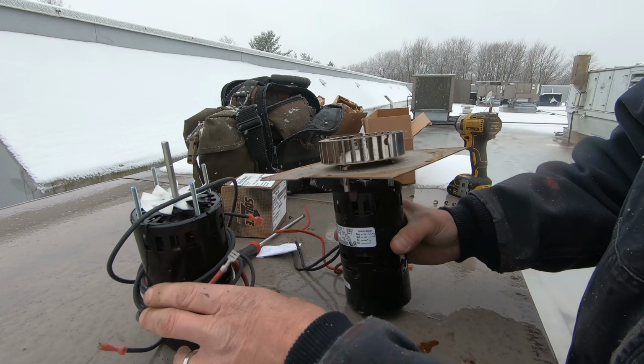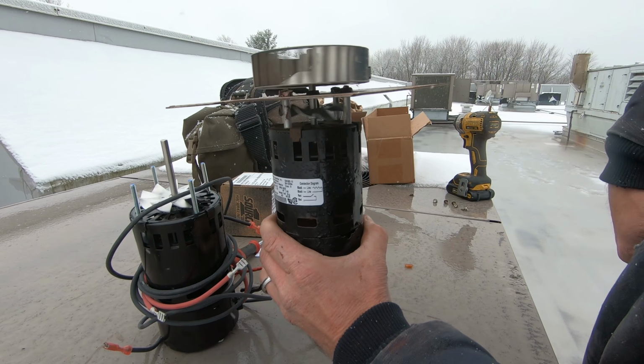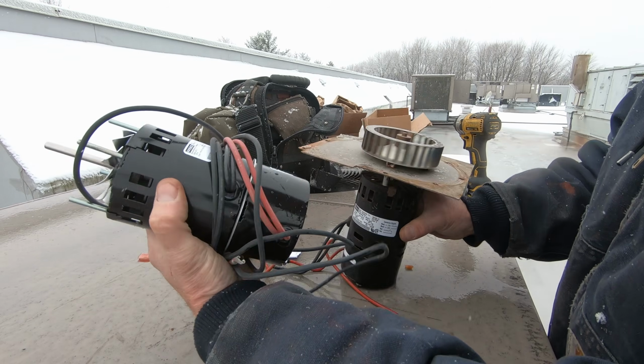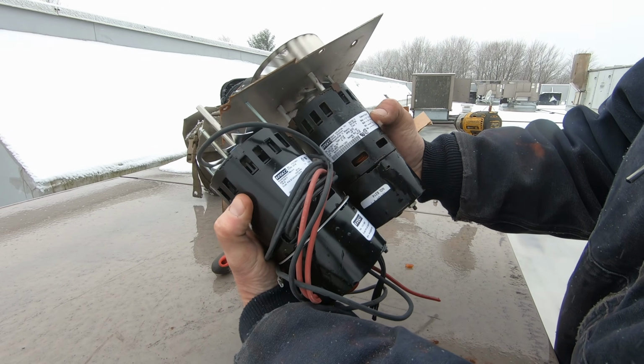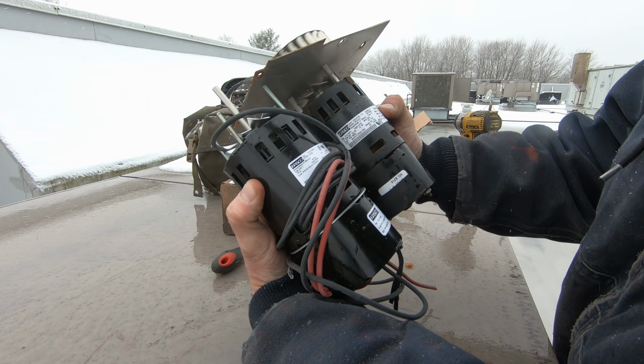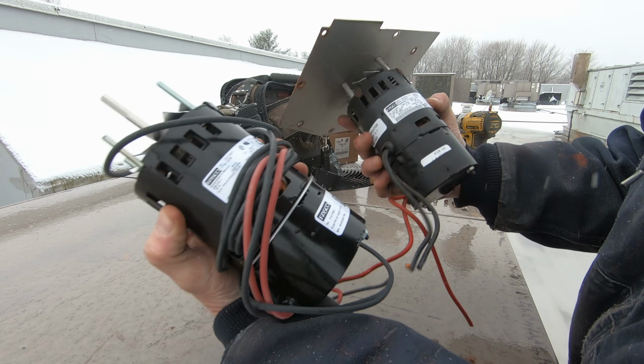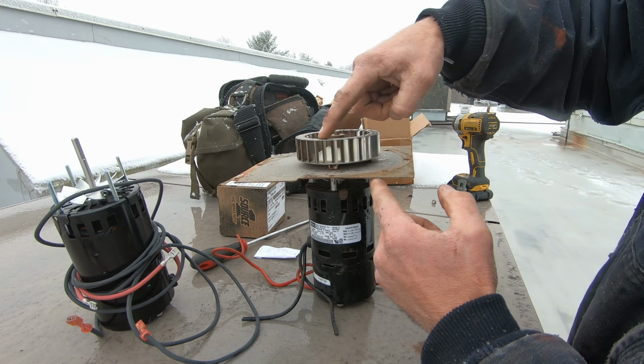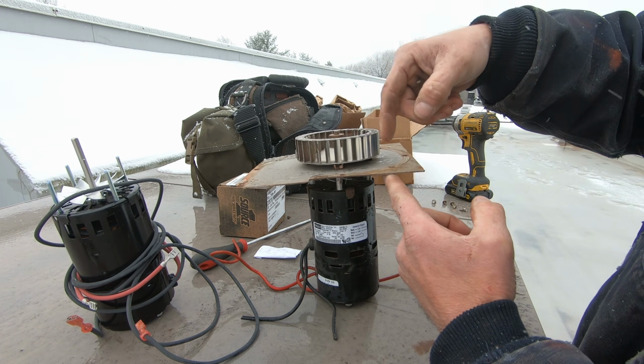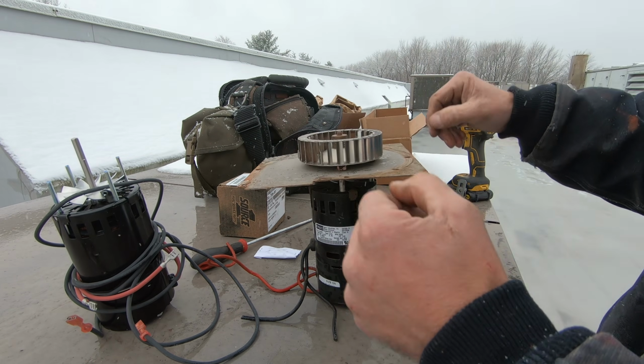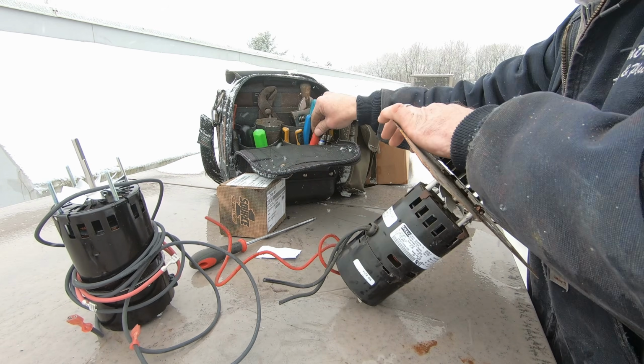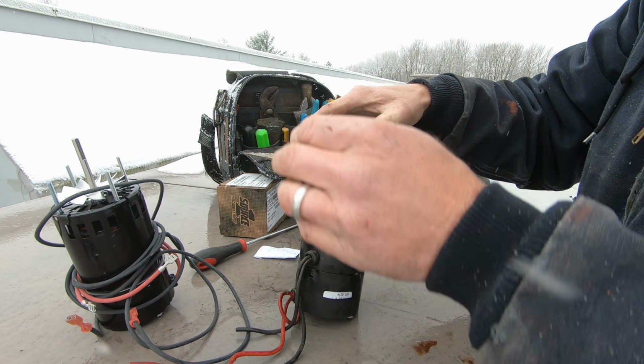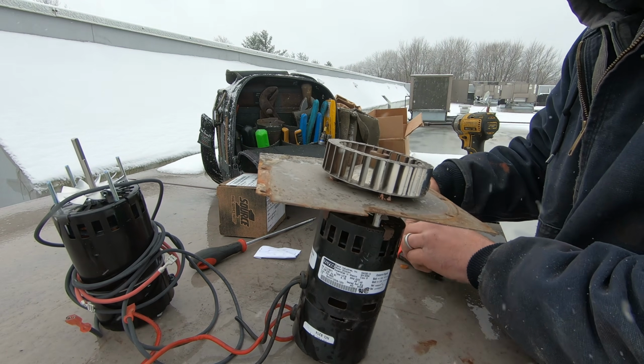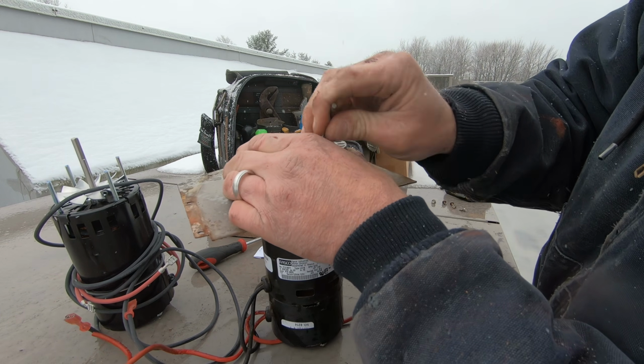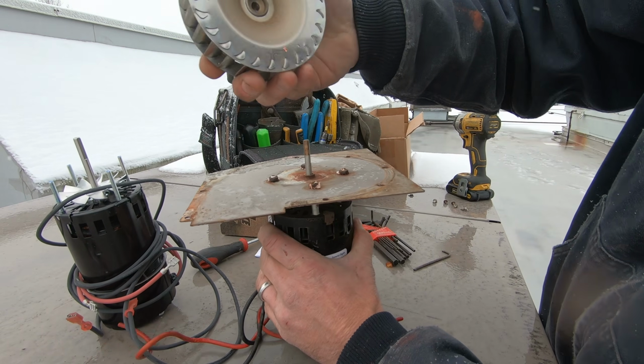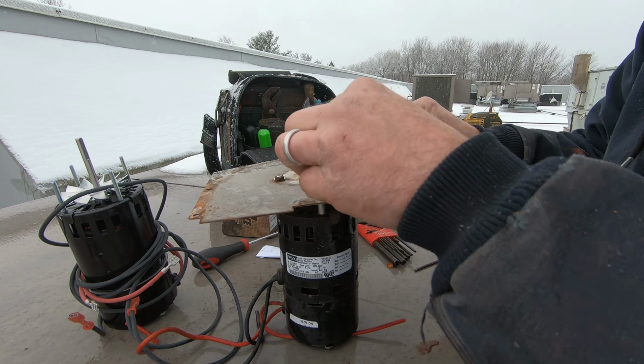All right, next step, replace this combustion blower. So we got our new motor here, we got our old one. Check the voltages, make sure they're good. We got a 208-230, we got a 208-230, so we're all set. We got to get this squirrel cage off, and we got to get this mounting bracket off. Get this wheel off, and that'll start the process. There we go, and it came right off, so we're good to go there.